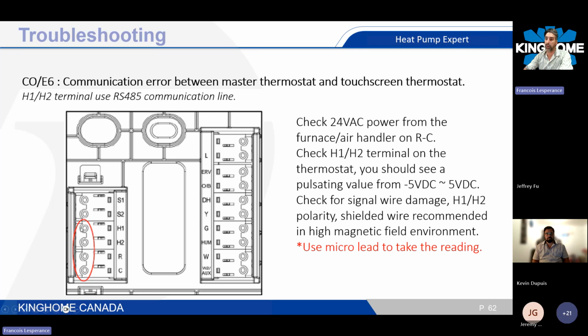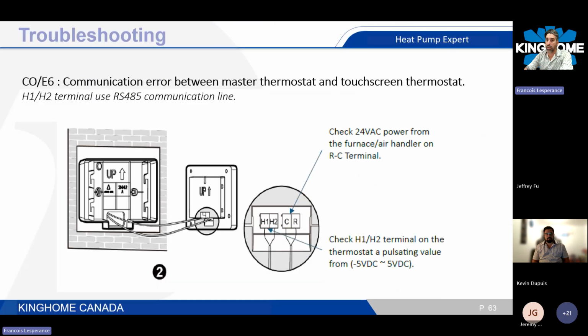But whenever you are testing that H1, H2 over here, you need to see a pulsating value from -5 to 5 volt DC. On R and C right here, you will have a straight 24 volts AC coming from your transformer from your gas furnace. So basically, the best way to measure it is you can pop up the touchscreen thermostat right here. So you see, you cannot just pull it out from the wall, okay?